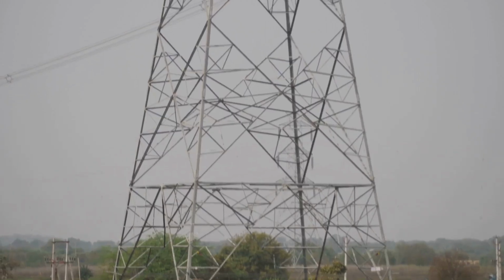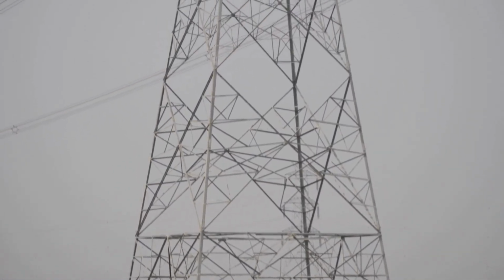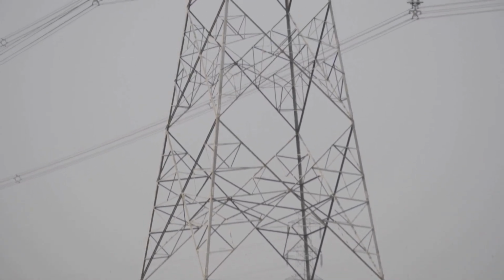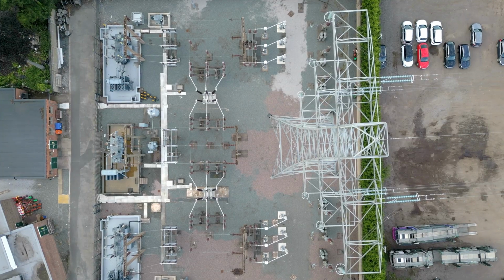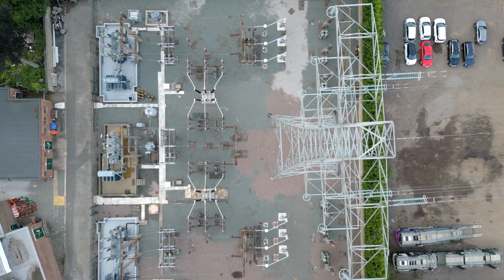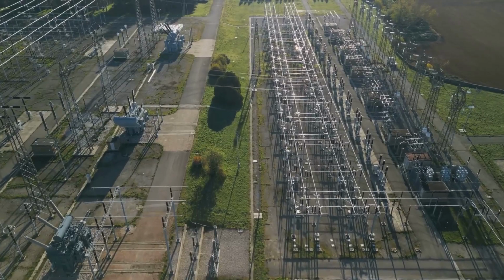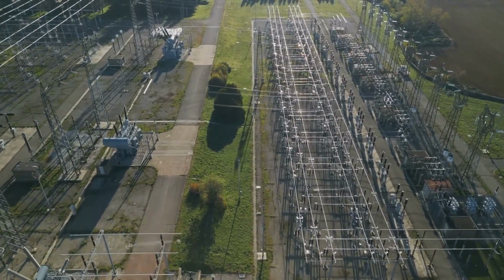Why does this matter in an FRT context? Because during faults, especially voltage sags, the grid often lacks sufficient reactive power. Voltage support becomes a localized, fast-acting need. DERs are expected to behave like miniature VAR compensators.